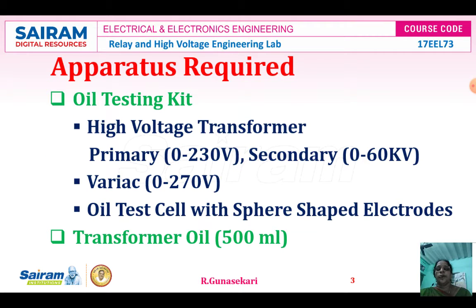Apparatus required: oil testing kit, transformer oil 500 ml. Oil testing kit consists of high voltage transformer. Primary voltage range is 0 to 230 volt. Secondary voltage range is 0 to 60 kV. Variac or auto transformer, the range is 0 to 270 volt. Oil test cell with sphere shaped electrodes.